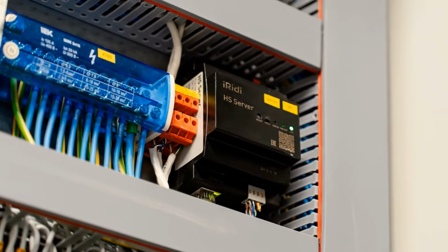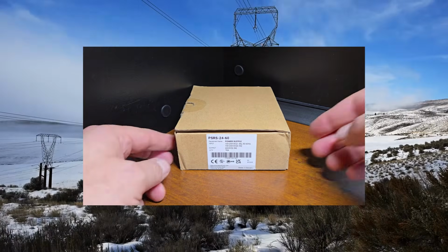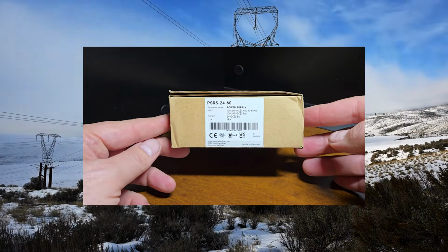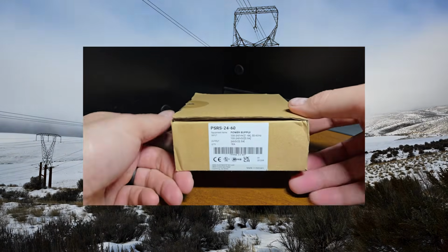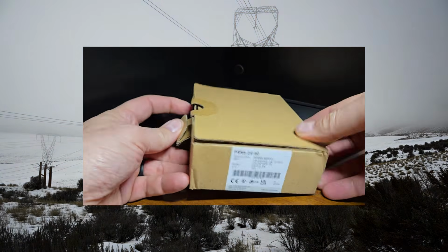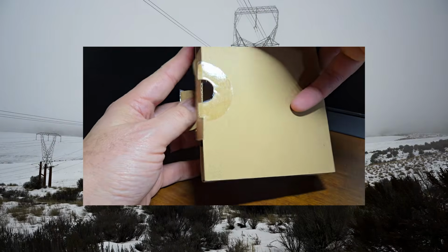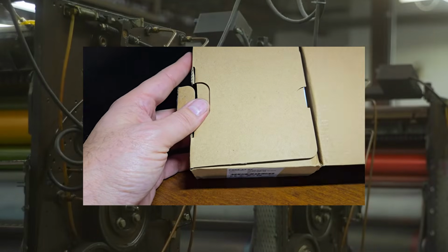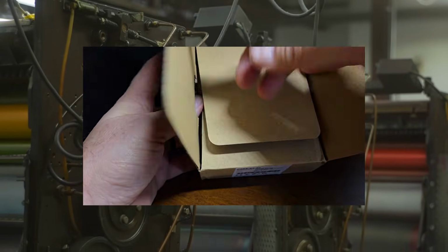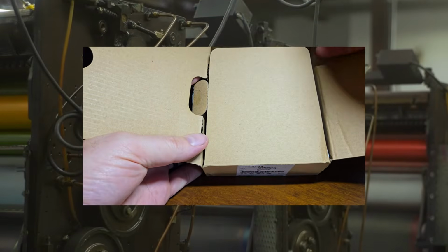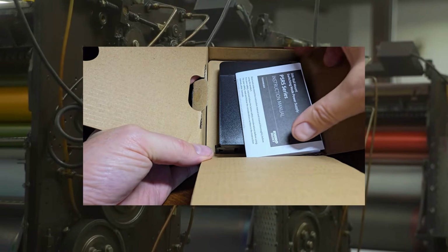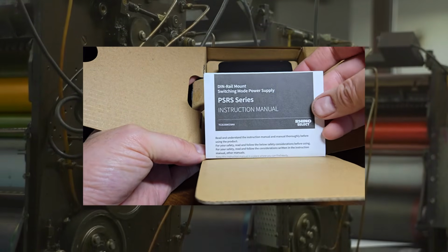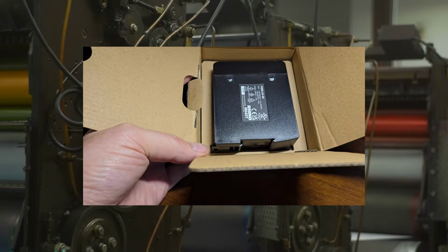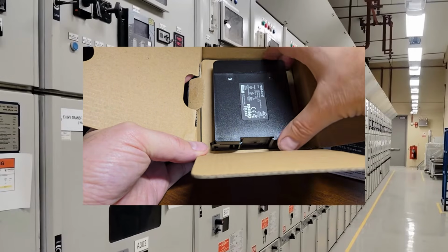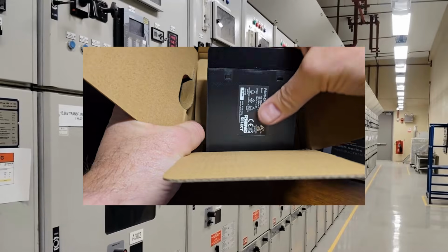Why do industrial cabinets need specialized power supplies? Walk up to any industrial control panel. The power coming into that cabinet is usually raw, high-voltage AC, perhaps 120V, 240V, or even 480V three-phase. It's powerful, but it's also noisy, fluctuating, and inherently dangerous. Conversely, the sensitive components inside the cabinet, the PLCs, sensors, HMIs, and safety relays operate in a different world. They require stable, clean, low-voltage DC power, almost universally 24V DC in modern automation.